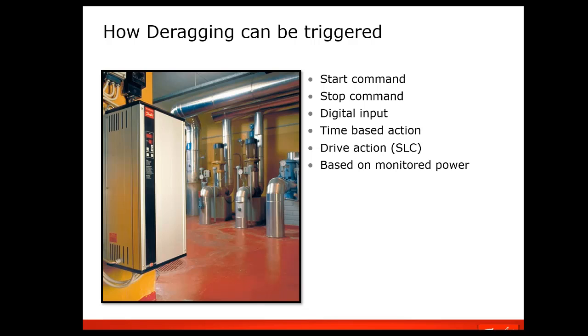As I've mentioned earlier, the deragging feature can be triggered right at start or at stop. It can be called upon based on a separate digital input. So even if it's running and you have a separate item, or based on an external timer, you can tell it to derag. It is built into or can be triggered based on the drive's internal time-based functions. The drive also has a smart logic controller, and that is one of the actions that can be programmed based on a sequence. And also it can be triggered based on power of the motor, knowing that it's using more power than normal, and can trigger that it needs to be deragged or declogged.